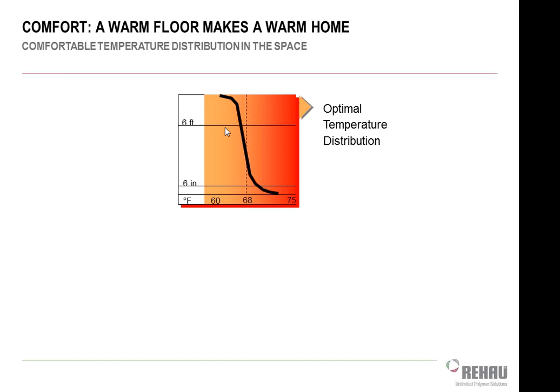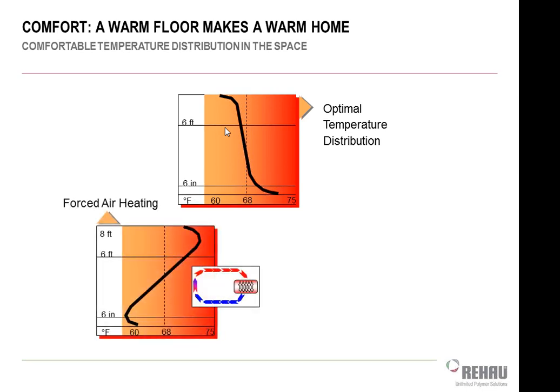If you keep that temperature within 5 degrees from the people's feet to their head, basically, they don't notice the temperature difference at all. However, if you have stratification, you might have, say, where the thermostat's located on the wall at 4 feet, it's 72 degrees. The stat's happy as can be, but down on the floor, it's 61 degrees, right? And then they'll have cold feet, and they'll feel that problem. That's true both residentially and commercially. So forced air systems don't do a very good job of keeping that stratification under control. As you can imagine, whether we're diffusing air from the floor or the ceiling, it's going to have a bias, right?